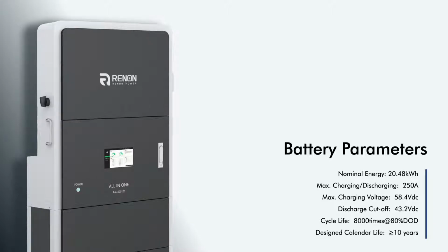This product also possesses a long cycle life. The system life can reach over 8,000 cycles, and its design calendar life is over 10 years. The cycle life and design calendar life of this low voltage model is also the same as the rest of the 2 products. As we can see, the nominal energy is 20.48 kilowatt hours, which is what the 020 represents, and the max charging and discharging current is 250 ampere. The max charging voltage is 58.4 volts, and the discharge cutoff is 43.2, which cannot be exceeded.